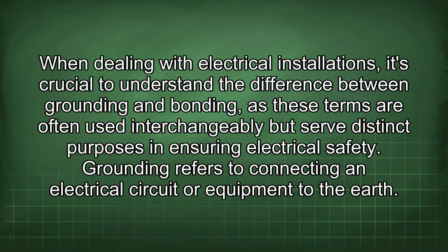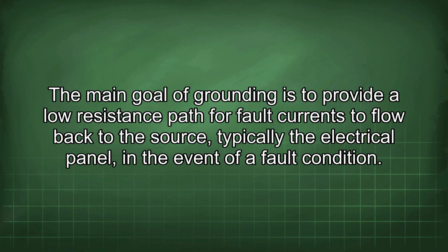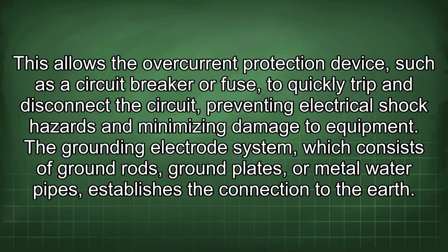When dealing with electrical installations, it's crucial to understand the difference between grounding and bonding, as these terms are often used interchangeably but serve distinct purposes in ensuring electrical safety. Grounding refers to connecting an electrical circuit or equipment to the earth. The main goal of grounding is to provide a low resistance path for fault currents to flow back to the source, typically the electrical panel, in the event of a fault condition. This allows the overcurrent protection device, such as a circuit breaker or fuse, to quickly trip and disconnect the circuit, preventing electrical shock hazards and minimizing damage to equipment. The grounding electrode system, which consists of ground rods, ground plates, or metal water pipes, establishes the connection to the earth.